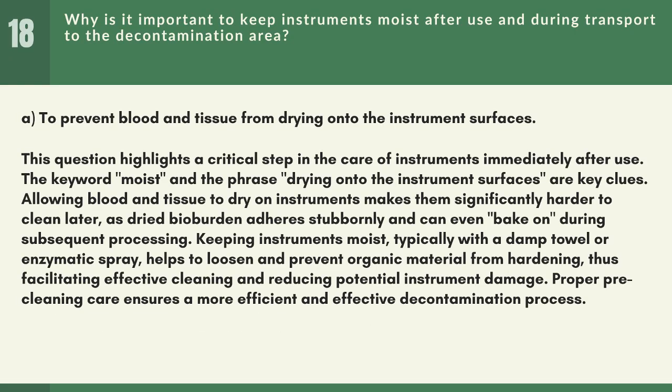Answer: A. To prevent blood and tissue from drying onto the instrument surfaces. This question highlights a critical step in the care of instruments immediately after use. The keyword moist and the phrase drying onto the instrument surfaces are key clues. Allowing blood and tissue to dry on instruments makes them significantly harder to clean later, as dried bioburden adheres stubbornly and can even bake on during subsequent processing.